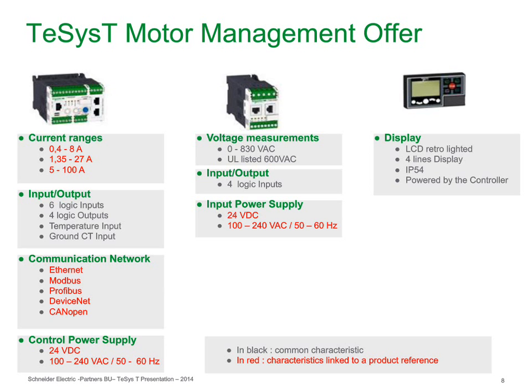We do have on the LTMR 6 inputs and 4 outputs. We have capabilities for both a temperature or thermistor input coming from a motor winding and also external ground inputs coming from an external ground CT. And then finally, you said it communicates. The industrial protocols we communicate on are Modbus, Profibus, DeviceNet, and CANopen. But we actually have Ethernet capabilities, and I'll talk a little bit more about those later on in the presentation.